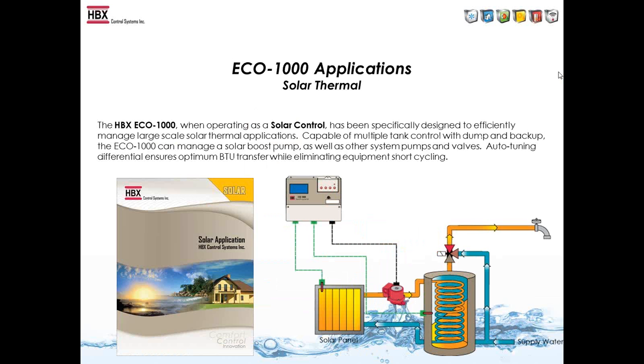With the ECO-1000, when you use the solar programming mode, it allows you to get into larger solar applications. So it's basically a differential control with a backup as well as having a dump contact on it. It has auto-tuning differential built onto it, so it will make sure you have the optimum BTU transfer. So it's going to change your delta T based on the running time of the pump while eliminating equipment short cycling.